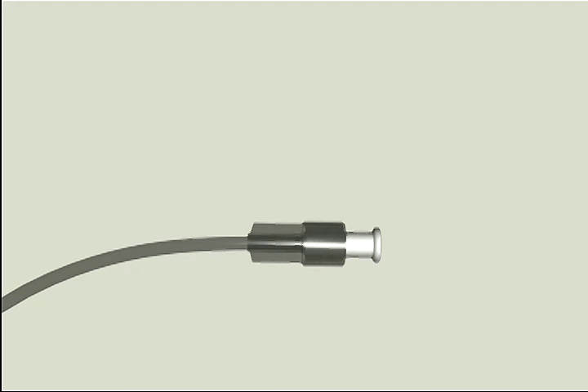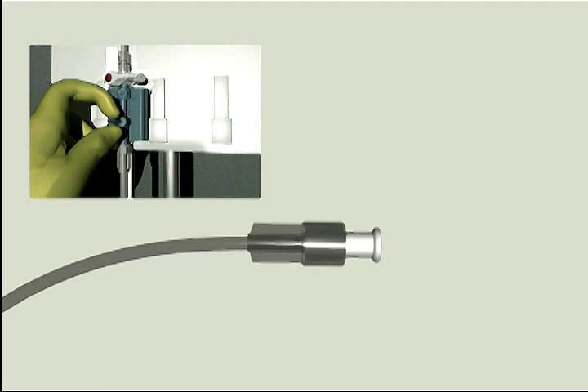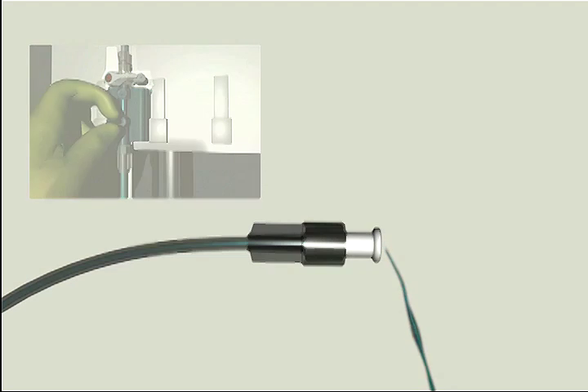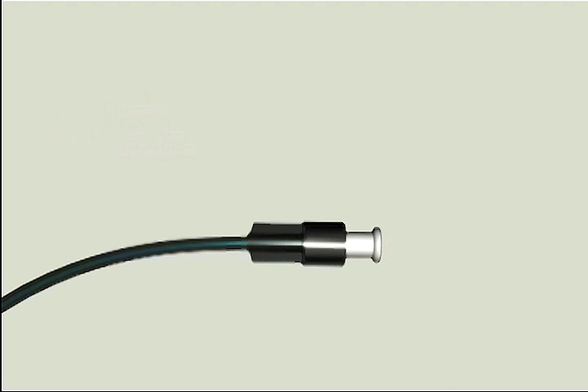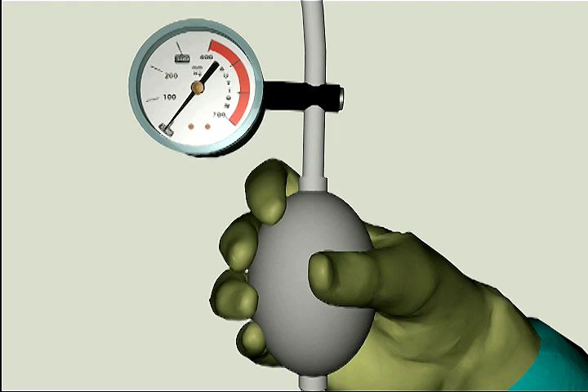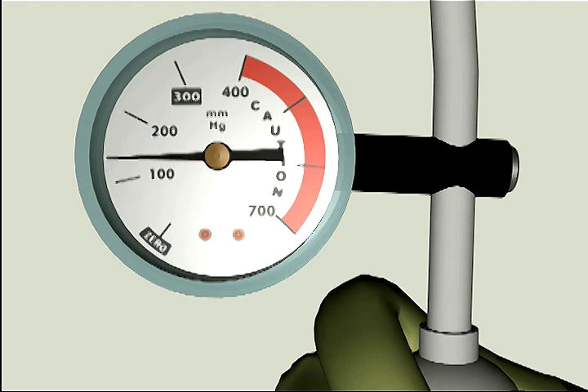Holding the pressure tubing at an upright 45-degree angle, pull the snap tab to flush the remaining part of the line through the end of the tubing. Step 5. Fast flush the TruWave transducer system. Pressurize the IV flush solution bag to 300 millimeters of mercury.